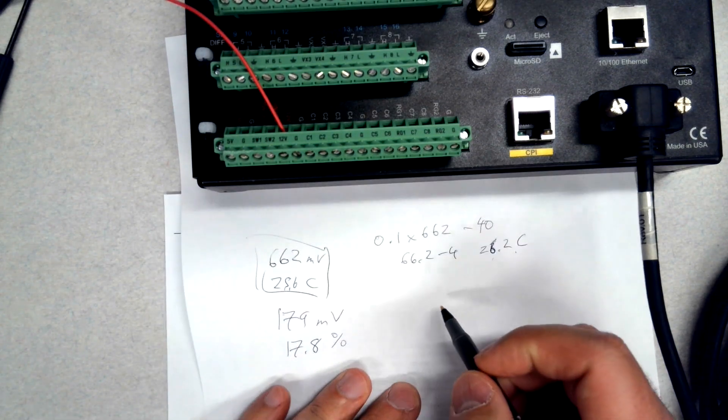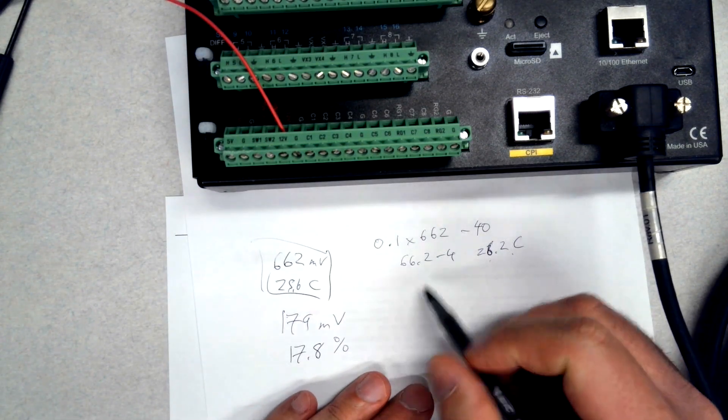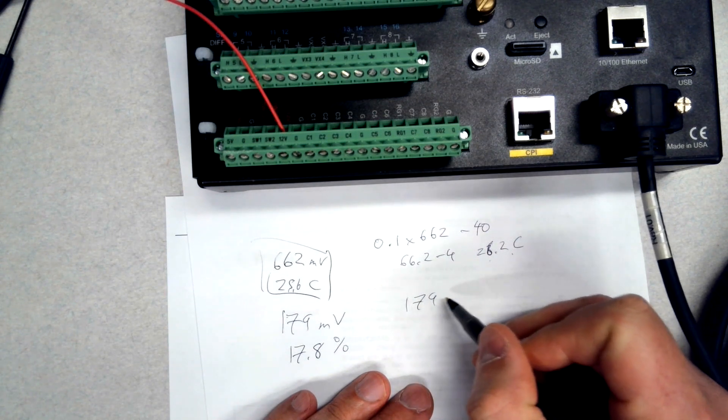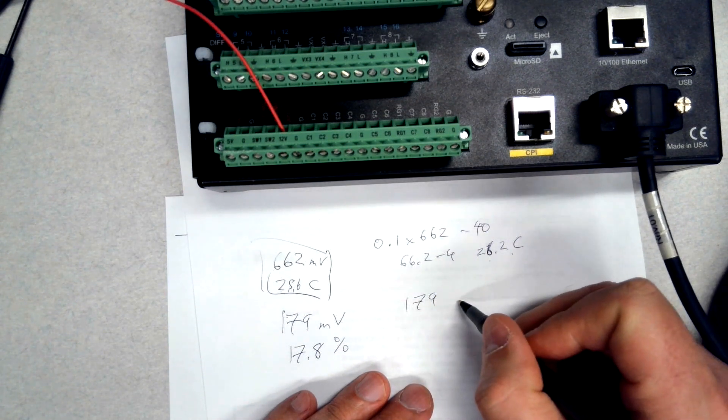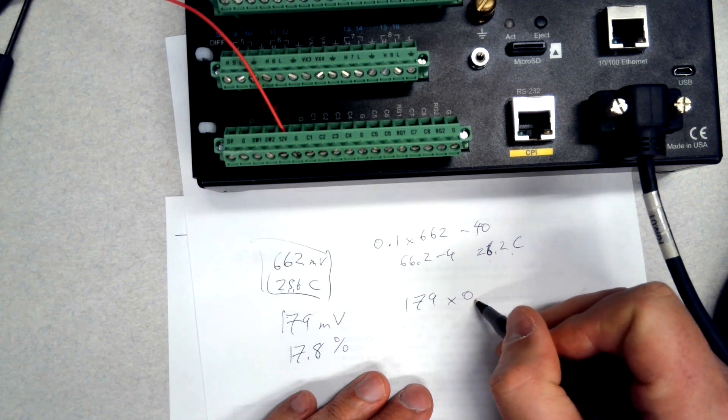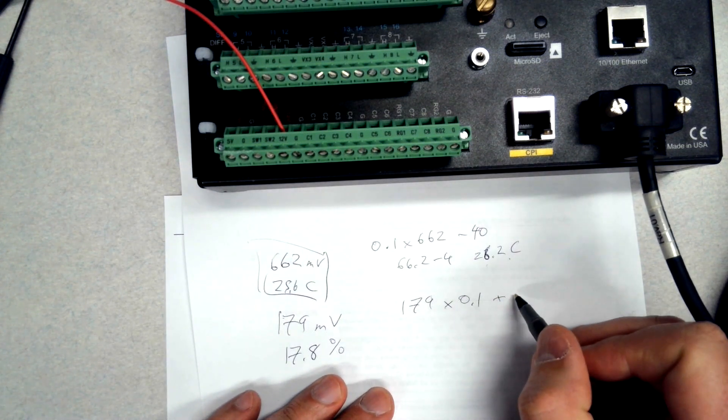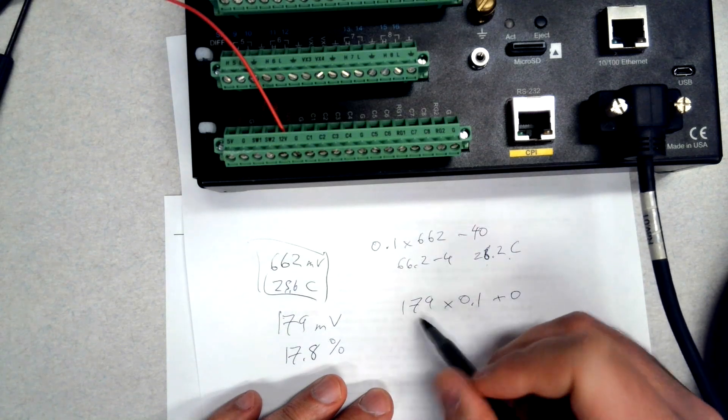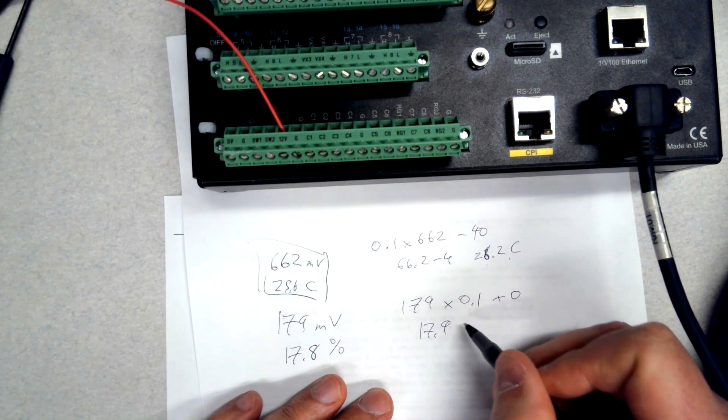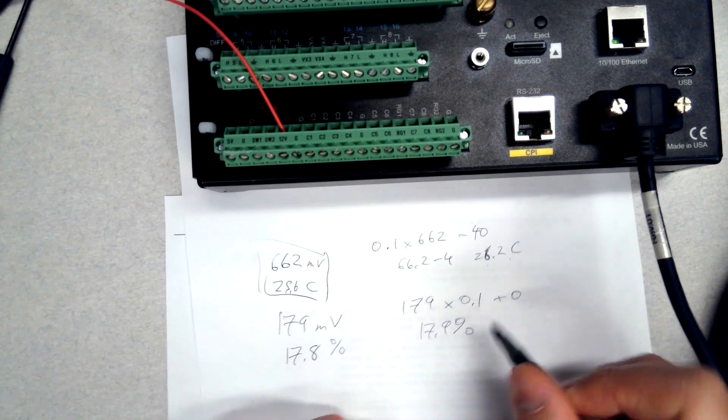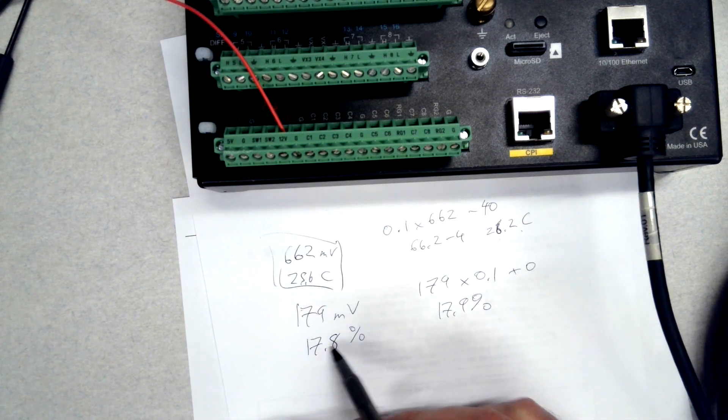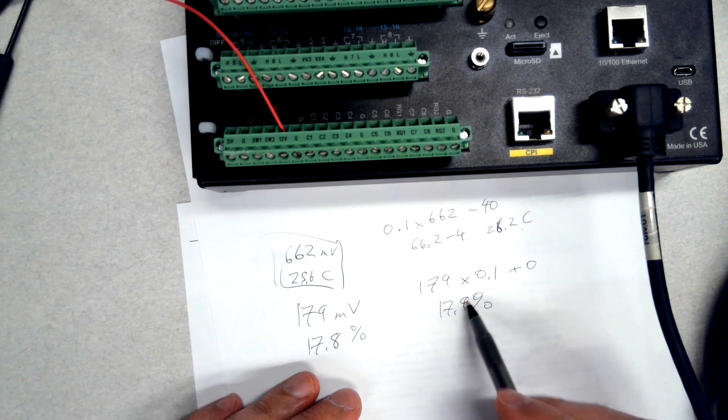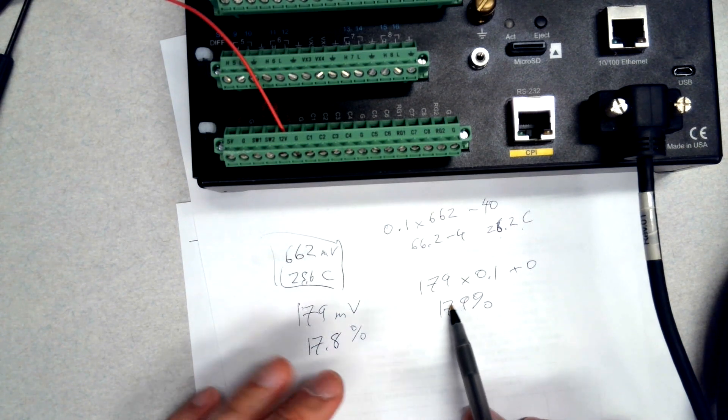For the humidity, we have the 179 millivolts. This one has a multiplier also of 0.1, but this one has an offset of zero, so that's going to be 17.9 percent humidity, which is really close to what the data logger reported. So what this indicates is the data logger is reading the sensor correctly.